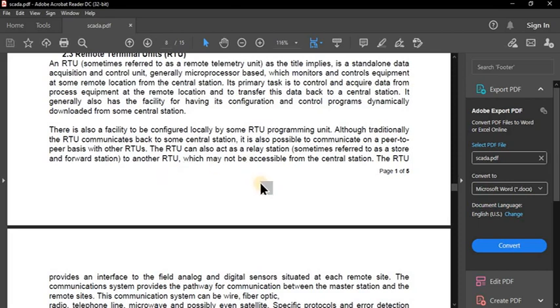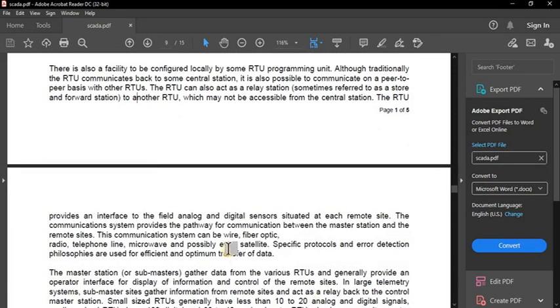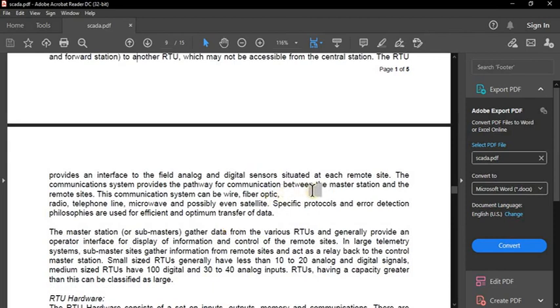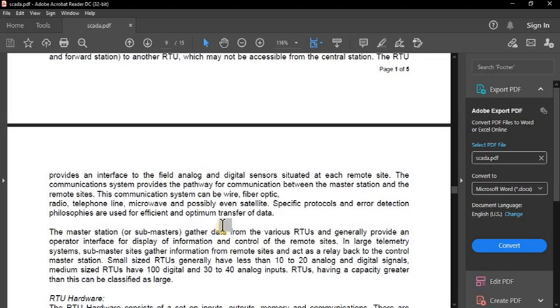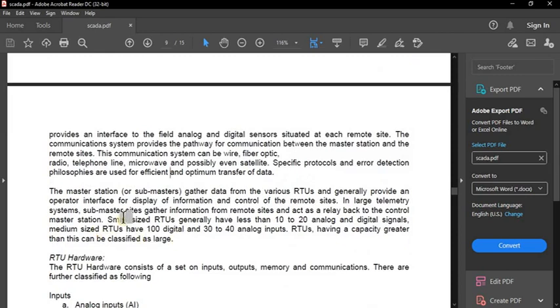The RTU can also act as a relay station to another RTU which may not be accessible from the central station. The RTU provides an interface to field analog and digital sensors at remote sites. The communication system provides pathways for communication between the master station and remote sites, which can be wire or fiber optics.